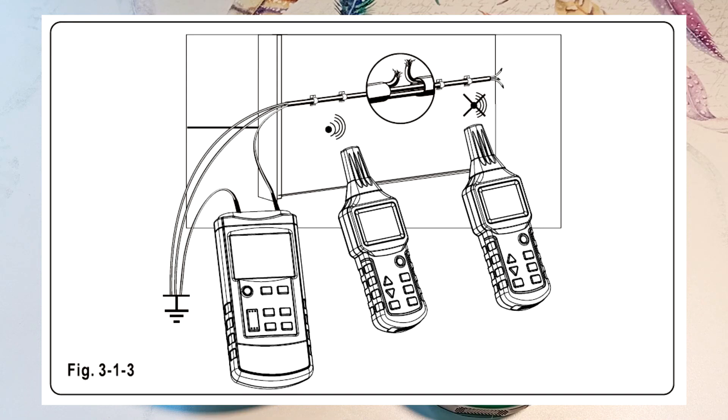In this figure we find a cable break. The circuit is de-energized. We connect the generator with one terminal to ground and the second to the broken wire. We ground the remaining conductors in the cable. This is done so that interference from the generator signal along entire cores does not travel further along the cable. In the place where the signal is interrupted, there is a wire break. To increase detection accuracy, it is also recommended to ground the other end of the broken wire.